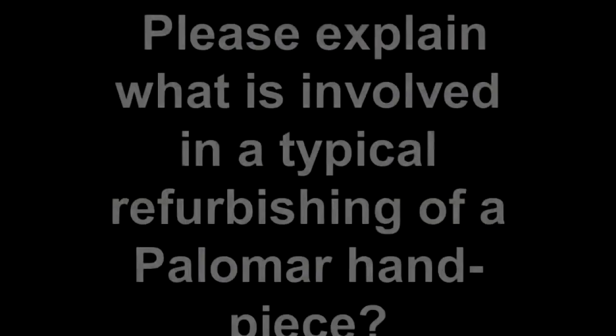You also got to be careful that the integrity of the safety mechanisms internally are compromised once they do open up the handpiece itself, and in doing so, again, if anything was to happen internally and they were compromised through this third-party repair situation, again, you've got a very, very dangerous situation, not just for the patient but also for the operator at the same time. So you have to be careful that it is certainly repaired by Palomar itself to ensure that the integrity of the handpiece is maintained.